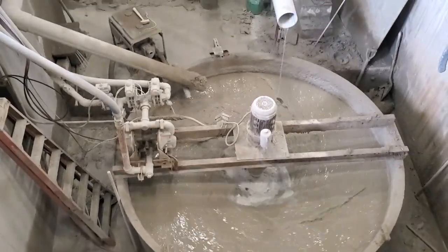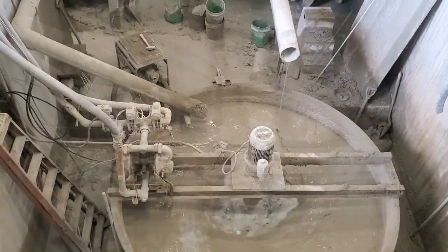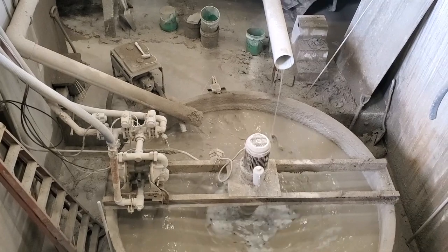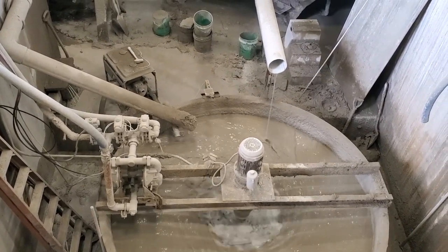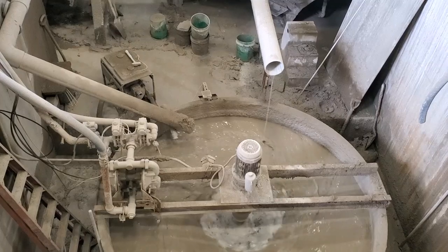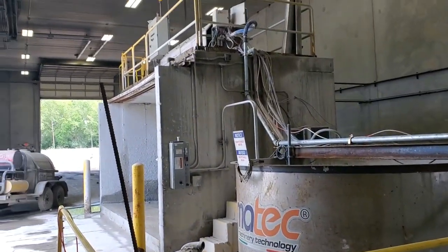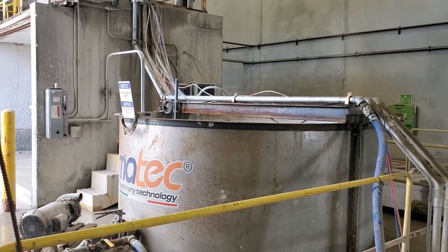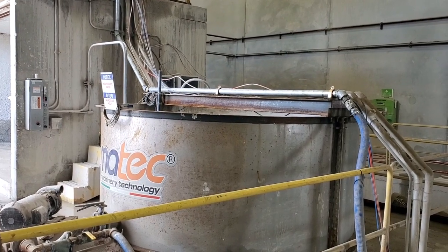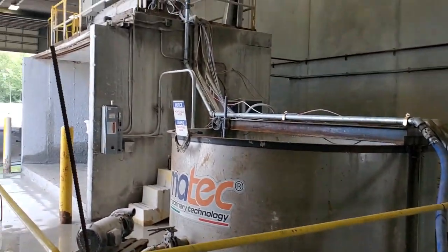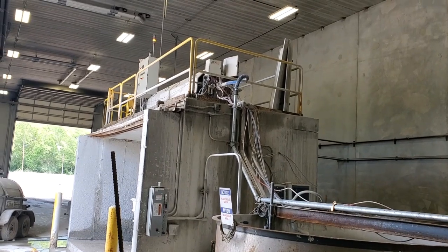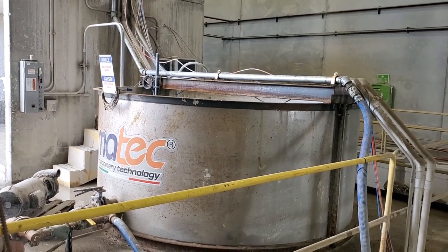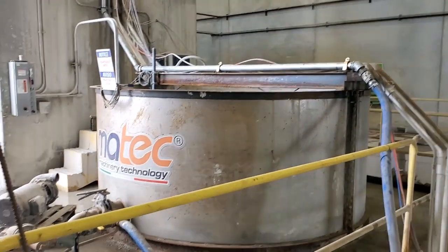It is. And what's going on inside this tank? This tank has a giant propeller in it that keeps the particulates floating in the water. Then the pump takes the water up top to the filter press, which filters out the particulate. The water then comes back down to this large tank, where it gets the pH treated. The filter press settles out all those very fine materials that you can't get with the settling tank. Then that water goes into the steel tank.